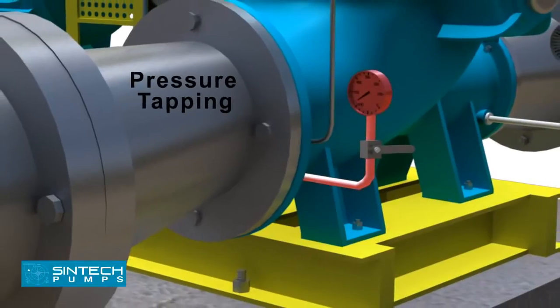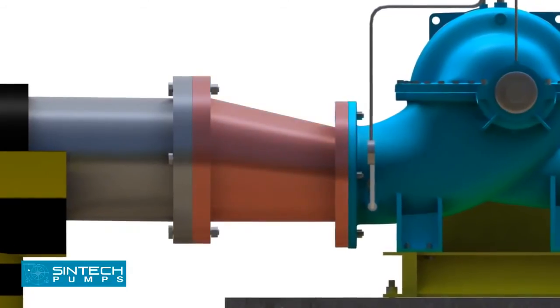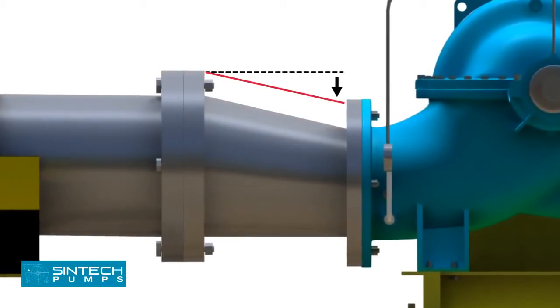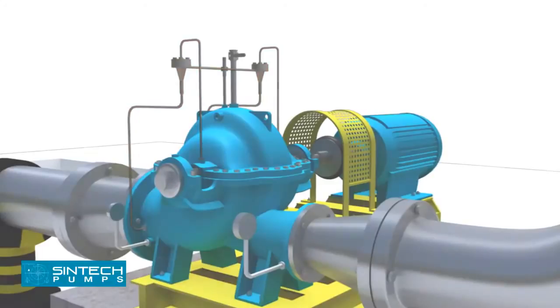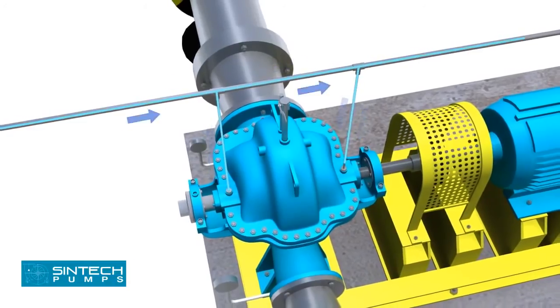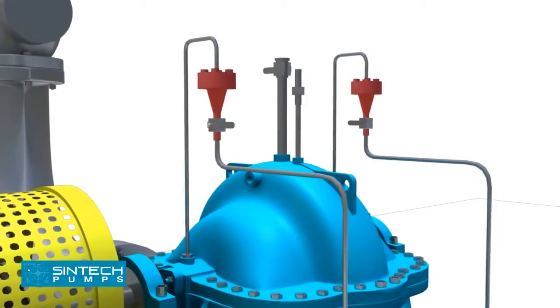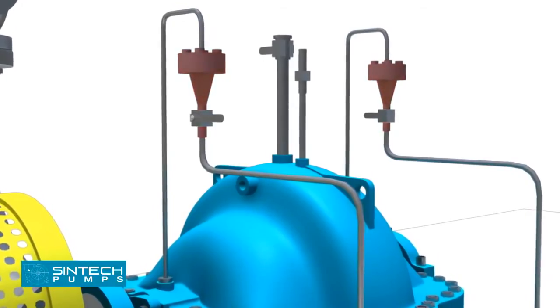There should be a tapping provided for installing a pressure gauge in the suction line. The reducer joining the straight length of pipe in the pump line should be an eccentric reducer, with the flat side as the top side. Stuffing box seal connections are usually made from the top of the pump casing. If the liquid being pumped is unsuitable for sealing, it is preferable to bring fresh cool water to the seal connections from an outside source. Centrifugal separators or other filters may be used to remove abrasive particles from the liquid being pumped if an outside source is not available.